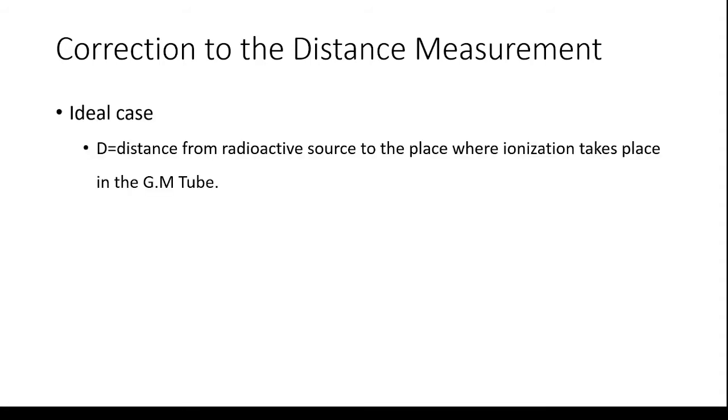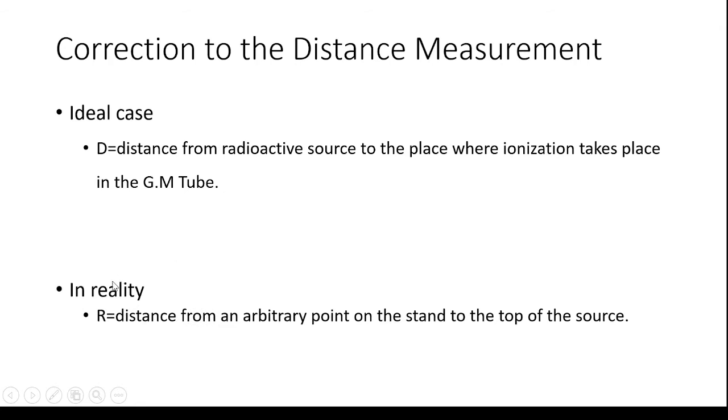Now the important thing is we have to make a correction for the distance measurement. In our ideal case, this D which you have measured is the distance from the radioactive source, the place where the ionization takes place in the GM tube. But in reality, the R which you are measuring is the distance from an arbitrary point on the stand to the top of the source as I have demonstrated in the diagram earlier.